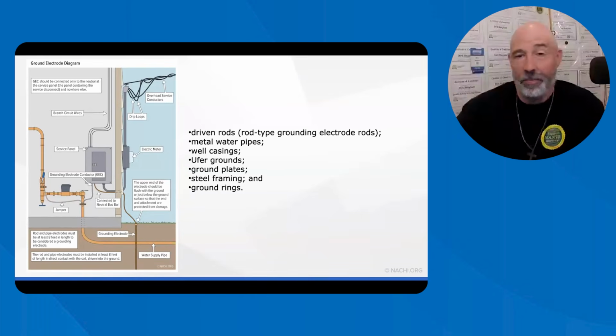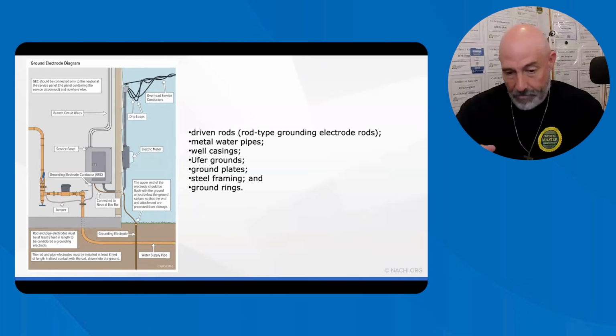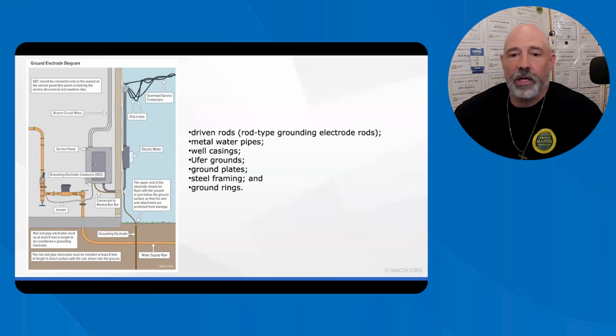Because most utility companies now install plastic pipes, like I've said, water lines are not to be used as a means of grounding anymore. So a lot of times your well casing is still metal, and that can be a system to ground. Anything that's metal in the ground basically could be a grounding wire. Now, gas piping should not be used as grounding electrodes, just FYI, for safety reasons. But in most areas, gas lines are required to be bonded to the grounding system. If they are likely to become energized, we want a place for that energy to go. And again, check out the NEC 250 area that is all about grounding and bonding.